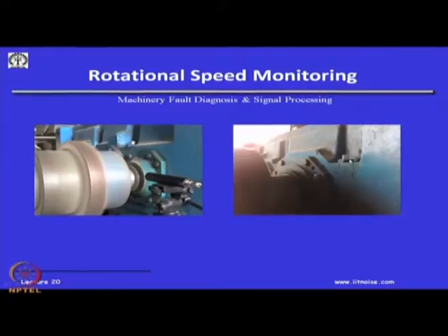And this is out of a gearbox. If you see here, we have a shiny white aluminum block. Actually, it's an aluminum block, wherein this is the casing of the gearbox. It is not possible to tap it at this site. So, all we did was put a mounting block and glued it with a cement. And if you see a couple of holes here, one hole here and a stud coming out on this accelerometer block, we can either screw on the accelerometer to measure the acceleration.